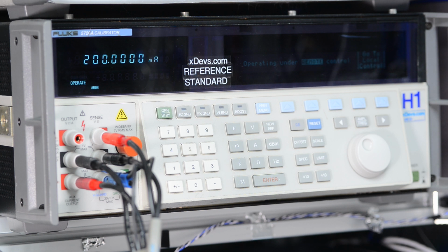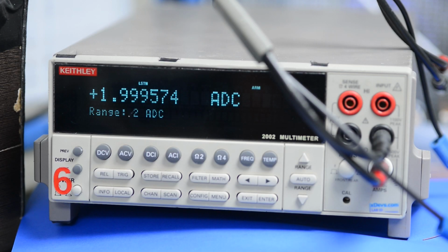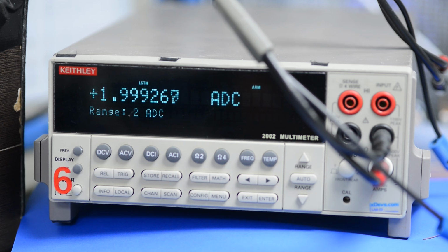Please note that higher current at 1 or 2 amps require quite a significant time to allow self-heating inside of the DMM to reach the stable point. In this 20 times faster than real-time video, you can see the self-heating with 2 amps applied to DMM, showing its effect. So the reading would either drop or increase, depends on the temperature coefficient of the current shunt inside 2002.